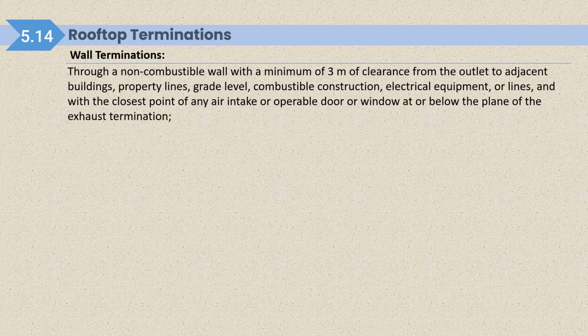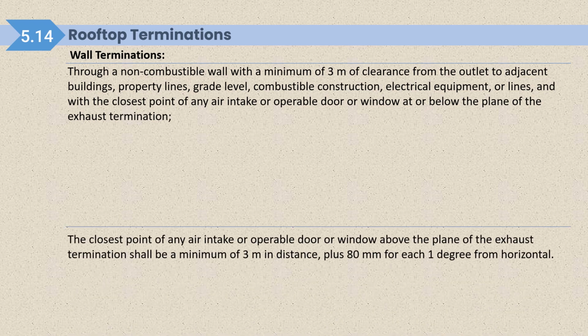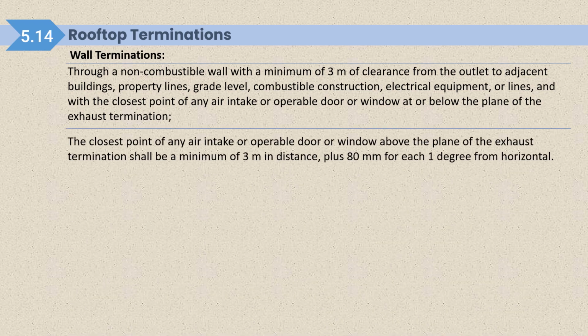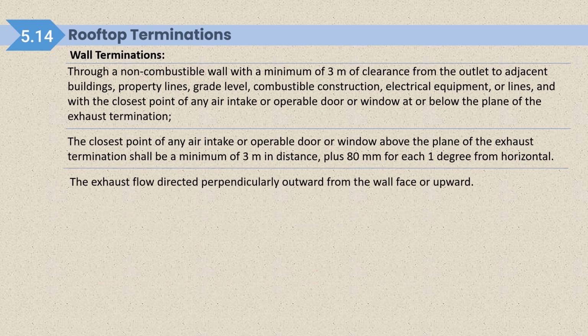In this section, wall termination is also mentioned: through a non-combustible wall with a minimum of 3 meters of clearance from the outlet to adjacent buildings, property lines, grade level, combustible construction, electrical equipment or lines, and the closest point of any air intake or operable door or window at or below the plane of the exhaust termination. The closest point of any air intake or operable door or window above the plane of the exhaust termination shall be a minimum of 3 meters in distance plus 80 mm for each 1 degree from horizontal. The exhaust flow is directed perpendicularly outward from the wall face or upward.